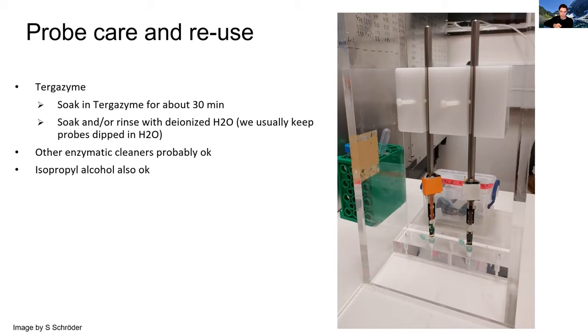If you get the probes with the cap already on it, that axis should be, I wouldn't be surprised if you could measure any misalignment between the cap and the probe shank. But my guess is that what Joe's referring to is probably the other axis. So the probe tilting up and down, which there are tight quality control specs on IMEC. There's a spec on that. You're supposed to only be able to have, I think one or 200 microns deflection of the tip relative to the base. But there can be a very slightly non-zero deflection. I think if you see like just one probe that you think is really bad, I would even see if you can get a replacement. But if you have in general, your probes are just a little bit off, I think there's probably not much you can do about it. We think in general that the sources of error in your targeting are probably more dominated by other factors than that.